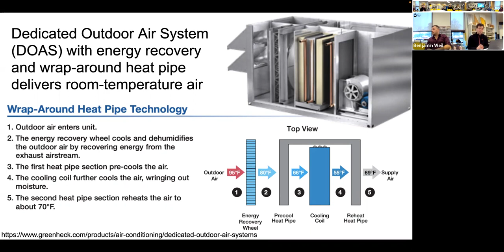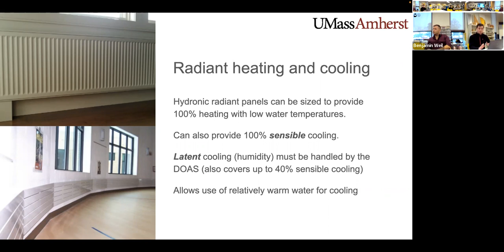For radiant heating and cooling, hydronic radiant panels can be sized to provide 100% heating with low water temperatures. It can also provide 100% sensible cooling, which can remove heat without changing the moisture content. Chilled water is used for both processes and allows the use of relatively warm waters for cooling. Latent cooling or humidity must be handled by the dedicated outdoor air system.